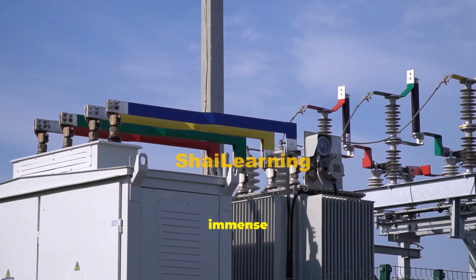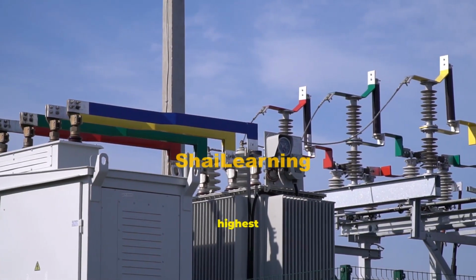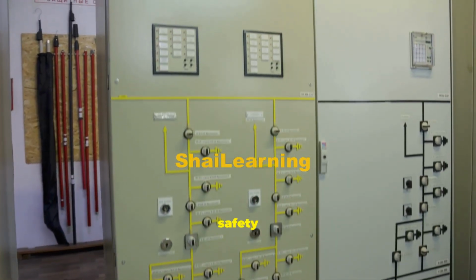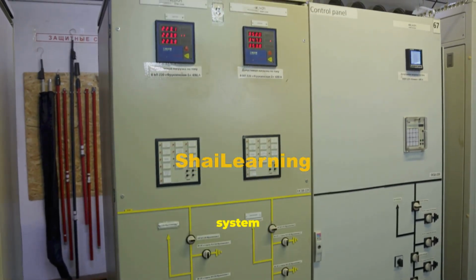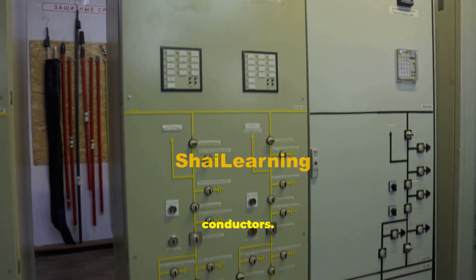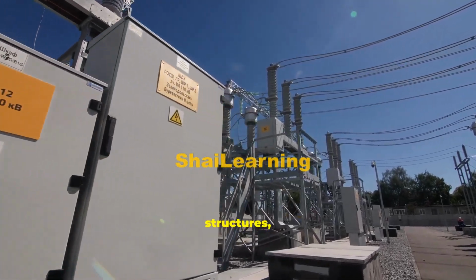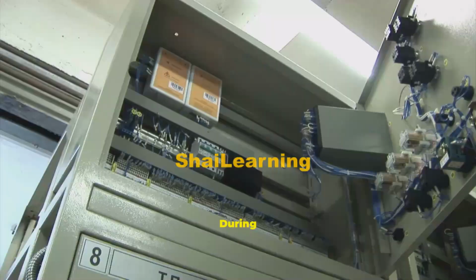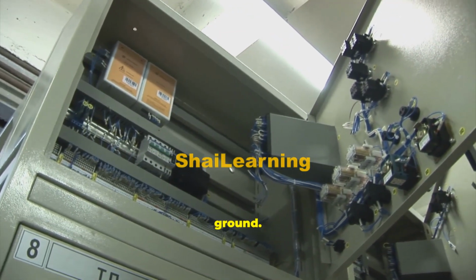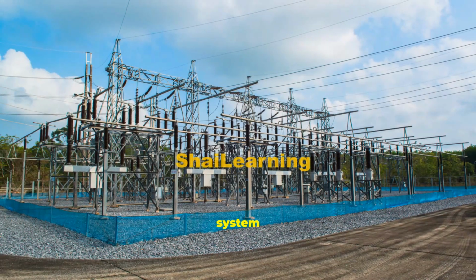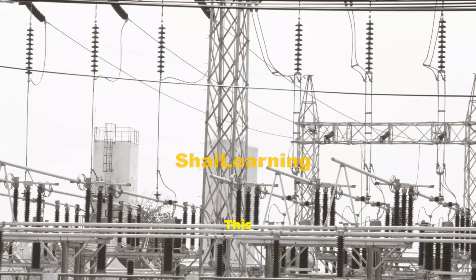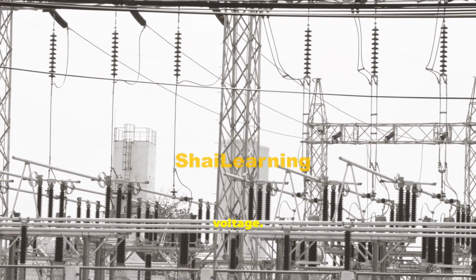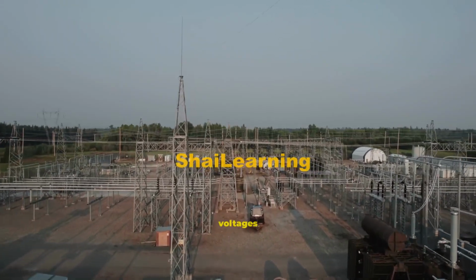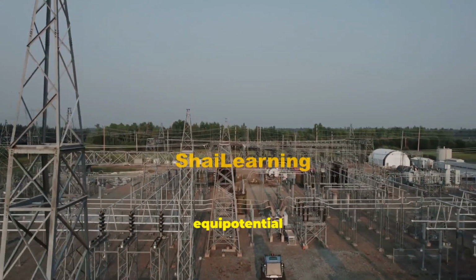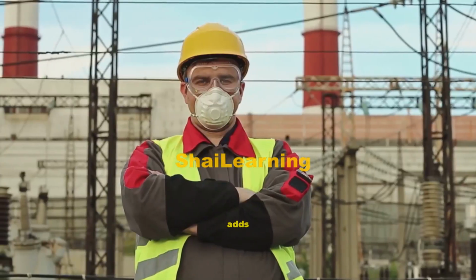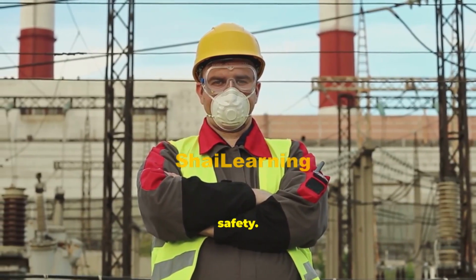In a place filled with such immense electrical power, safety is the absolute highest priority. One of the most critical safety systems in any substation is its grounding system, a network of buried copper conductors. It connects metallic structures, equipment frames, and fences. During a fault, large currents flow into the ground. A properly designed grounding system safely dissipates this current. This protects against touch voltage and step voltage. A well-designed grid keeps these voltages below lethal levels, creating an equipotential zone. Crushed rock adds surface resistance and further increases safety.